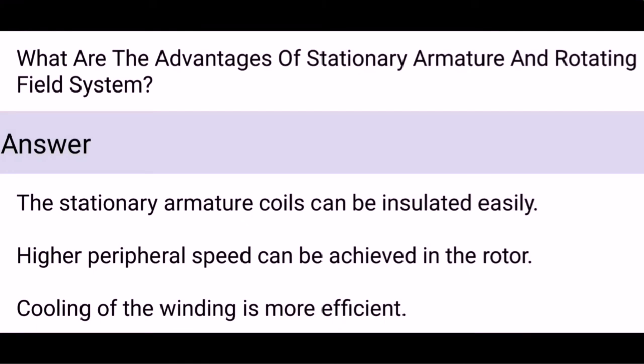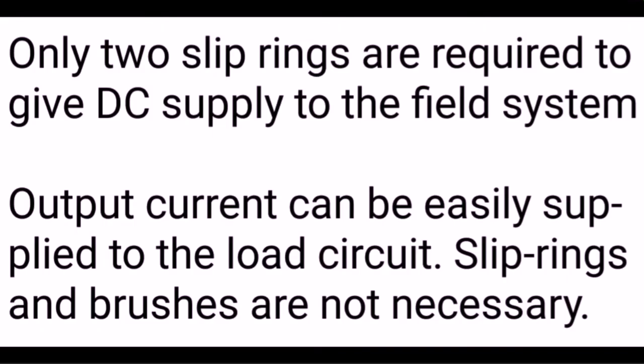What are the advantages of the stationary armature and rotating field system? The stationary armature coils can be insulated easily. Higher peripheral speed can be achieved in the rotor. Cooling of the winding is more efficient. Only two slip rings are required to supply DC to the field system. Output current can be easily supplied to the load circuit, and slip rings and brushes are not necessary.